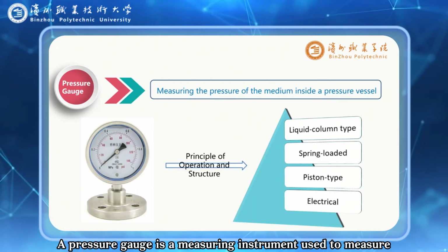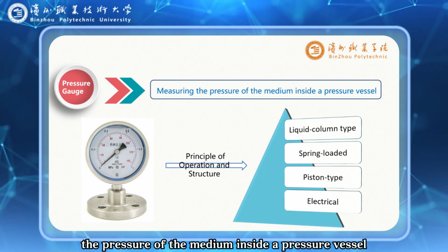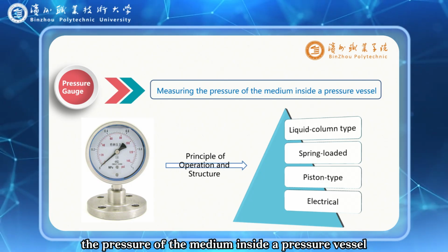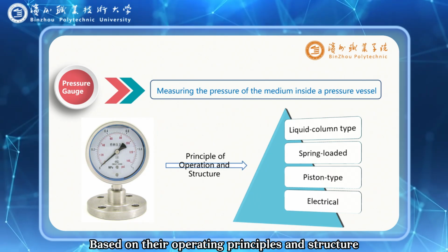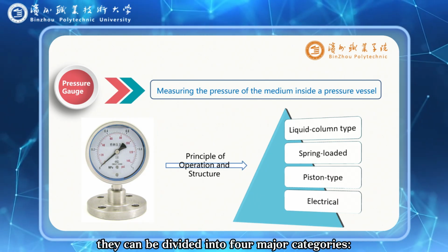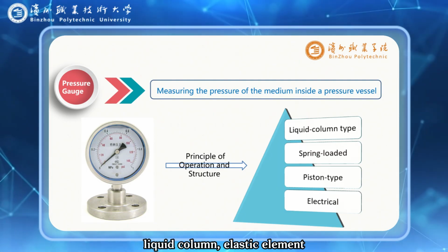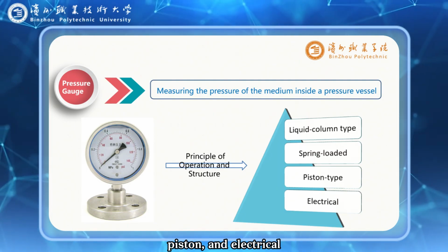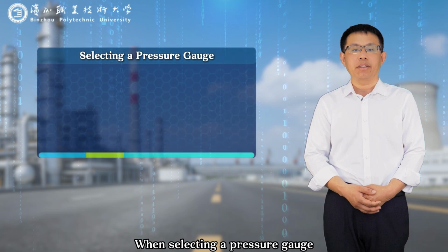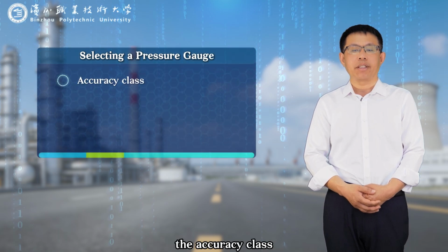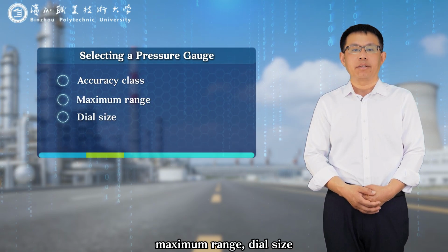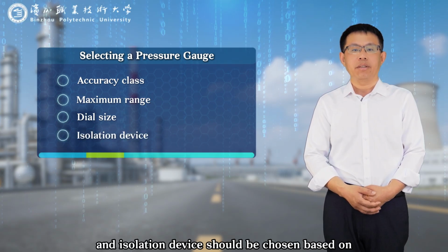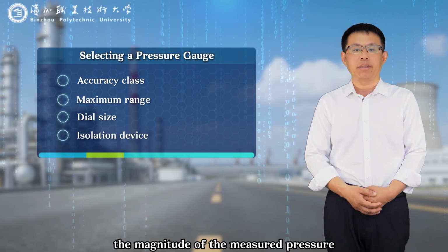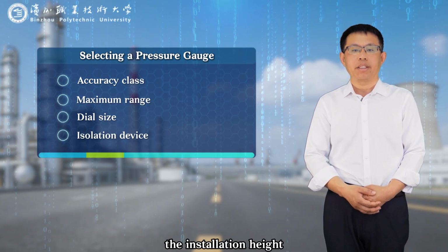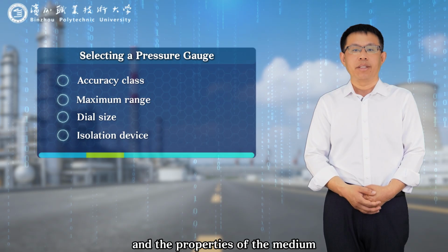A pressure gauge is a measuring instrument used to measure the pressure of the medium inside a pressure vessel. Based on their operating principles and structure, they can be divided into 4 major categories: liquid column, elastic element, piston, and electrical. When selecting a pressure gauge, the accuracy class, maximum range, dial size, and isolation device should be chosen based on the magnitude of the measured pressure, the installation height, and the properties of the medium.